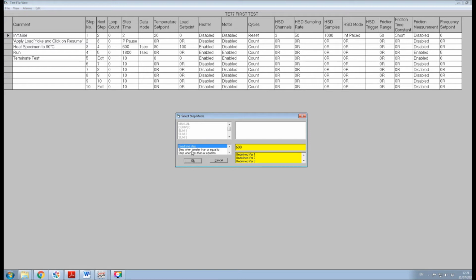As well as programming a fixed time for a step, the step time can also be programmed as a conditional step using the associated parameter box. There are a number of conditions that can be selected. In this case, I have chosen step when greater than or equal to. Select any one of these options and a browse list of parameters is presented. I am then prompted to select the source of the conditional parameter, with the choice being from a manual or derived channel or a live data channel from the SLIM unit. As our choice in this case is a live input, SLIM is selected, and then specimen temperature from the list of channels. The trigger value is then entered in the yellow box.